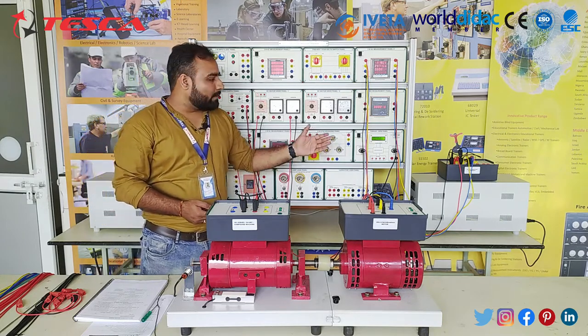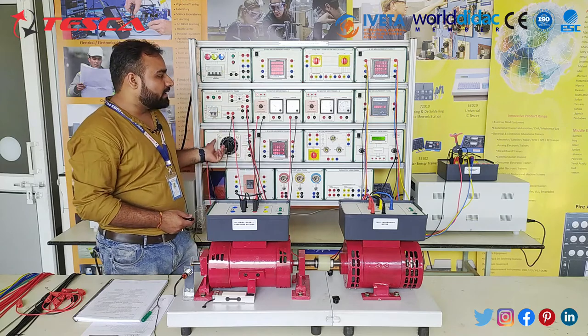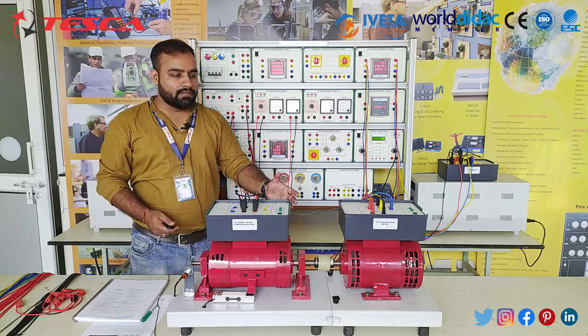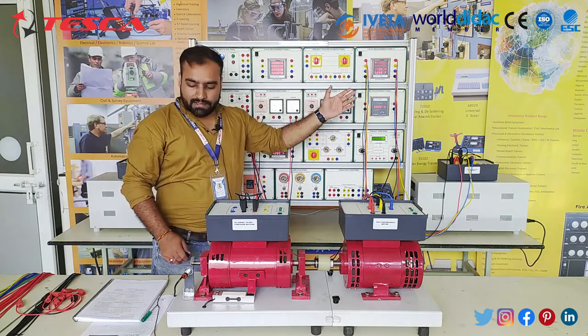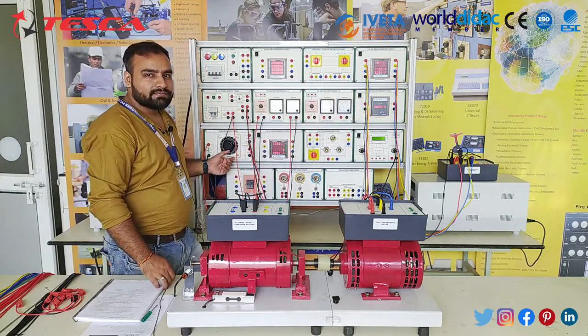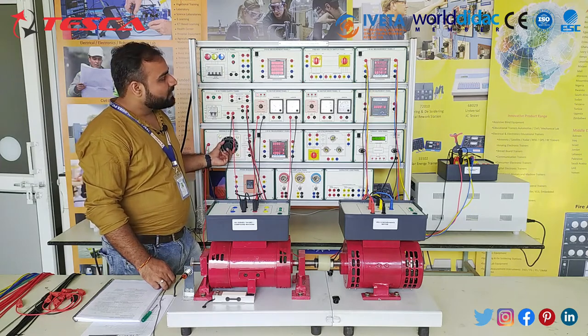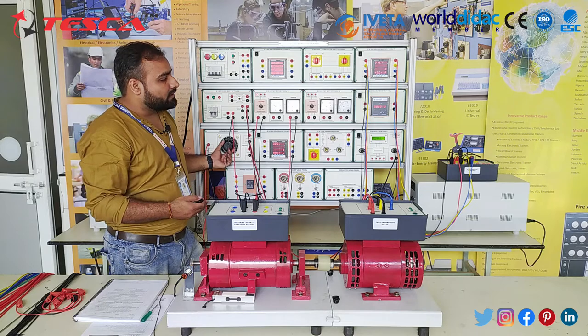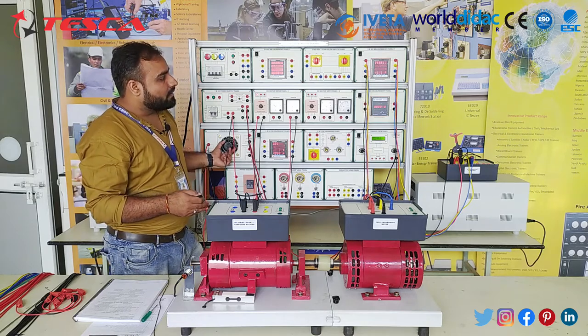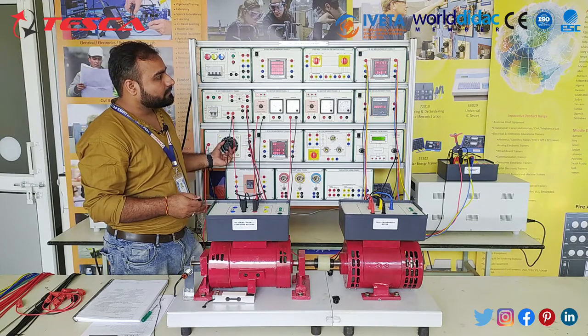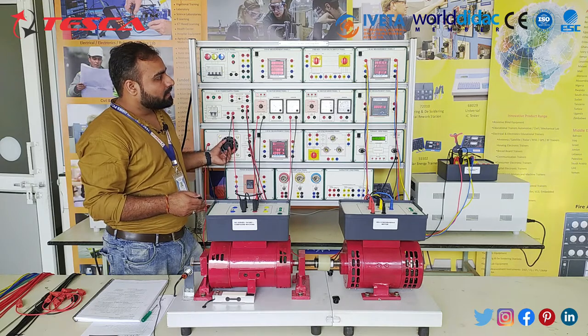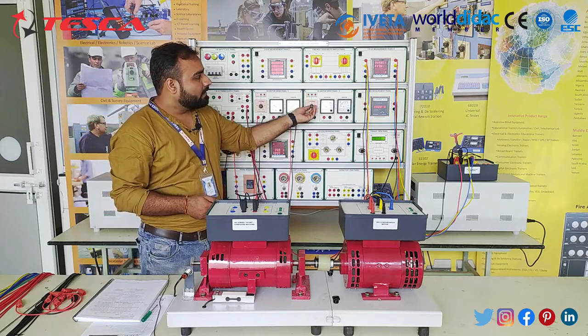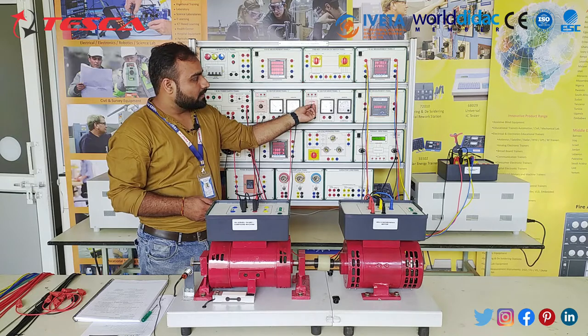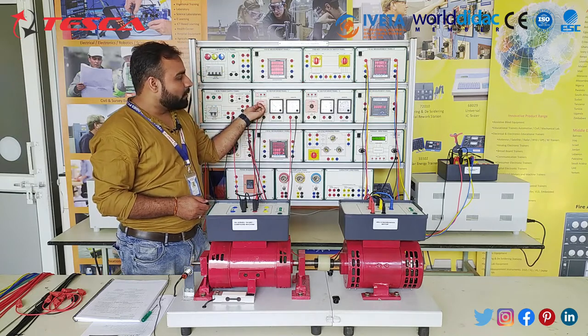So here, now the RPM is 3000. We gradually increase the DC supply to the field of the synchronous generator so that voltage generation can be observed on the three-phase measurement panel. Here you can see, as I am increasing the voltage, the RPM goes down and voltages are induced in the synchronous generator. Increase the voltage up to 380 volts and then match the frequency to about 50 hertz by increasing the RPM of the motor.